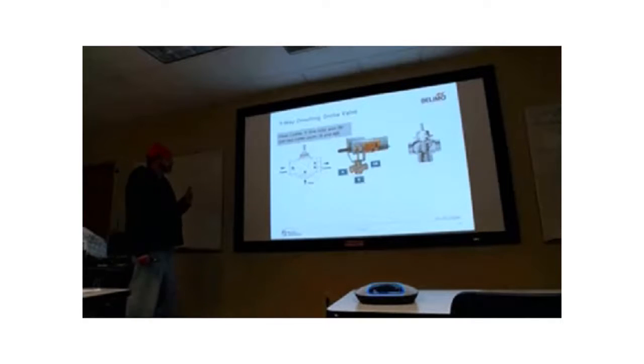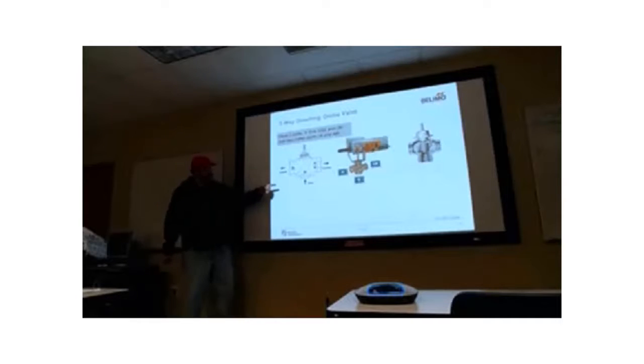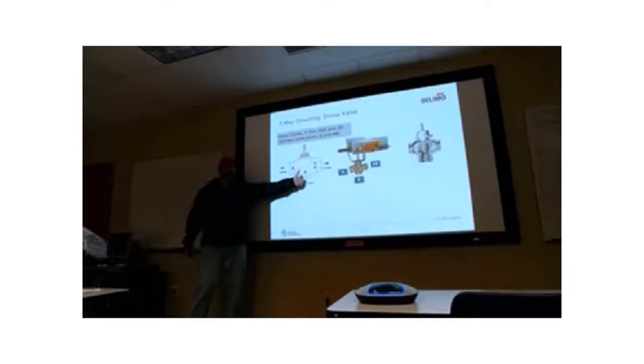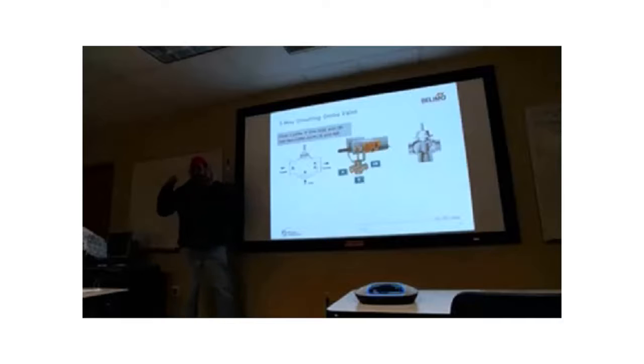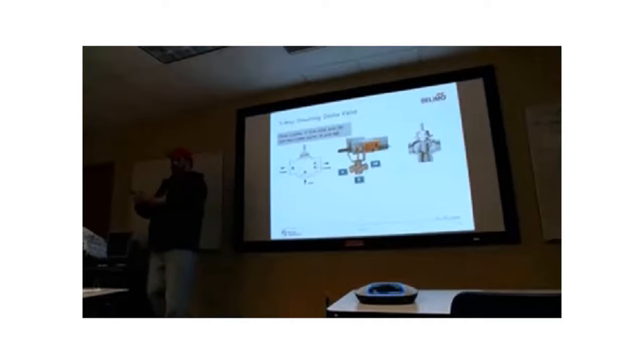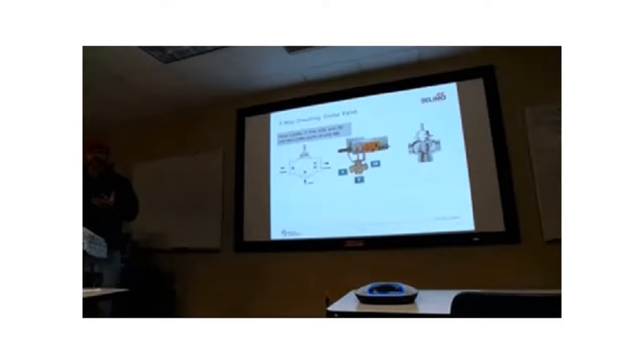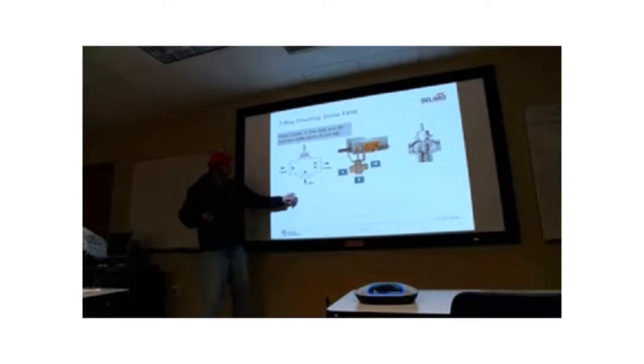But note this. This is a really important note if you're dealing with globe valves. What's the common port here? B, right? B. So it comes in here. It goes that way. It goes that way. Here's the key for field stuff. If you're looking at a valve, it's a globe valve, and you don't know whether it's mixing or diverting, the way that you can determine, if you know that this is the inlet port, that is going to be the common port, because in a diverting globe valve, the common port is always opposite the stem, because that's the physics of how that thing works. It has to work where the water comes in and goes that way or that way.